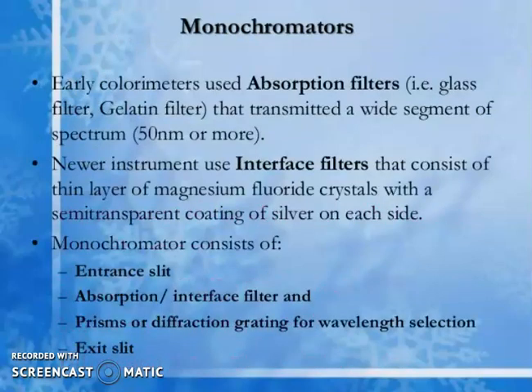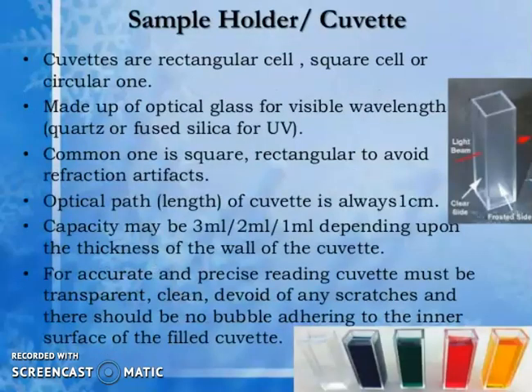Early monochromators used absorption filters such as glass filters and gelatin filters that transmitted a wide segment of the spectrum. Newer instruments use interference filters consisting of a thin layer of magnesium fluoride crystal with a semi-transparent coating of silver on each side. A monochromator consists of an entrance slit, absorption or interference filter, and a prism or diffraction grating for wavelength selection, plus exit slits.